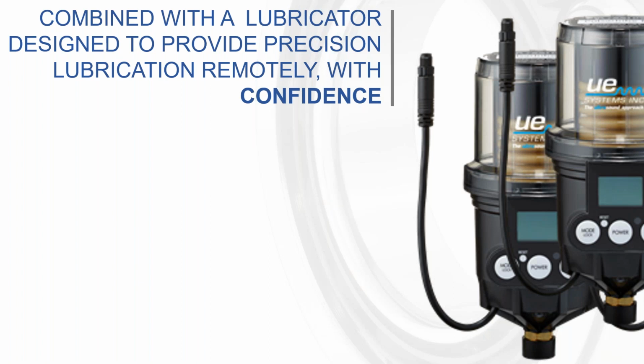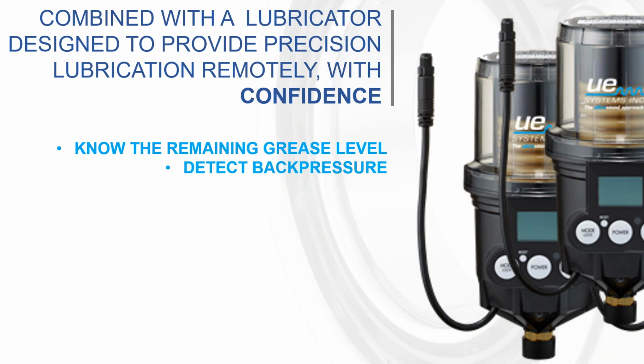So what can go wrong with these lubricators? The first thing is they're autonomous. They're sitting out there in our plants, and we hope that they're doing their job. Even if we know we might be over greasing a little bit or under greasing, at least they're putting grease into the bearing, right? But they're autonomous. So how do we know how much grease is left in them? What if there's a blockage in that grease line, in the grease path coming from that single point lubricator? Now, these are two very, very common issues. In fact, a lot of people we talked to created a time-based maintenance schedule to check these, when the purpose of these was to eliminate time-based lubrication. So it's very counterintuitive.